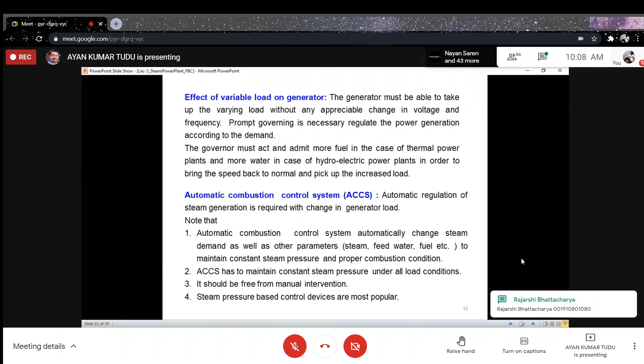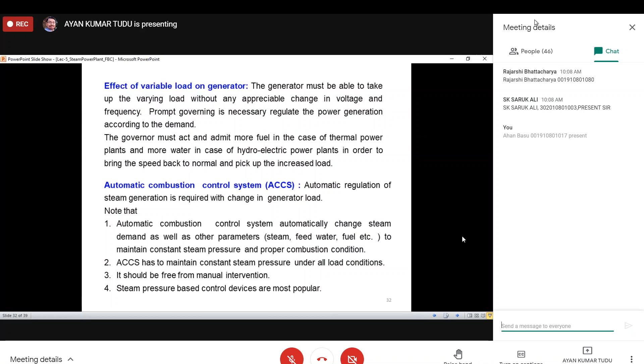Now, what we can do again, as you can see, is that this ACCS, the automatic combustion control system, has to maintain constant steam pressure under all load conditions. It means whenever there is a change in the load, the ACCS should be able to maintain that load condition, and maintain the constant steam pressure throughout the steam power plant.